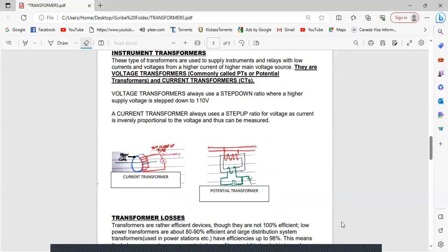So a potential transformer, especially with the instruments, that's why it's called here instrument transformers. For your voltmeter on your MSB, it is always going to be a step down transformer, and accordingly whatever the voltage is over here will be calibrated to give you a 440 volt reading, even though it is a step down transformer.